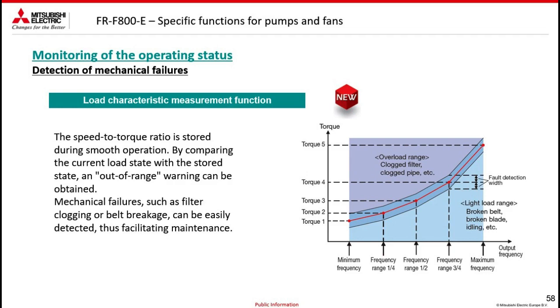Another appreciated function is the monitoring of the operating status to detect mechanical faults. It is possible to activate functions to have the inverter independently create a graph showing torque values at certain frequency values. Once the torque curve has been defined, it is useful to understand if there are mechanical problems. Once the optimal curve has been defined, when I read a torque higher than the predefined optimal one, it means that I could have mechanical blockages. Instead, if I read a torque lower than the predefined optimal one, it means that there could be another problem, such as in the case of belt pulley transmission, or a broken or slipping belt.